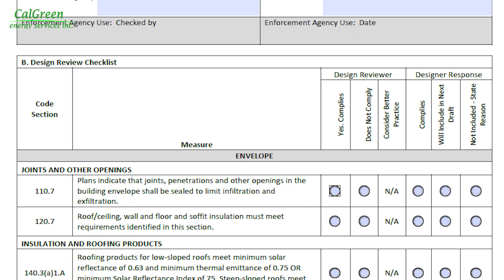Amendments to the CalGreen Code are published under the City of Los Angeles Green Building Code, but there are no changes to the commissioning section. This means the CalGreen Code sets the standard for new projects over 10,000 square feet in Los Angeles. Additionally, the California Energy Code also requires commissioning for projects over the same size threshold. Both codes, authored by the California Energy Commission, are intended to function together as a single process. The Energy Code includes a few additional requirements, such as completing the NRCC-CXRE commissioning form. For simplicity, we'll refer to commissioning as CX throughout this video.